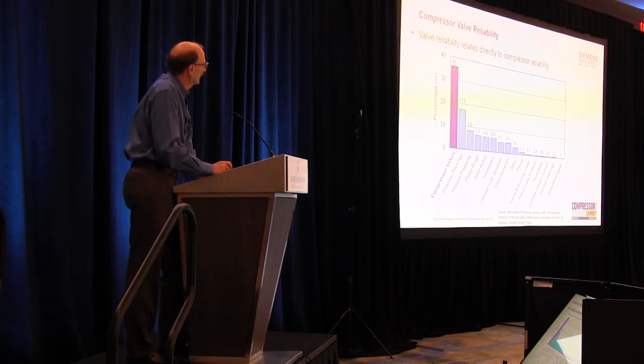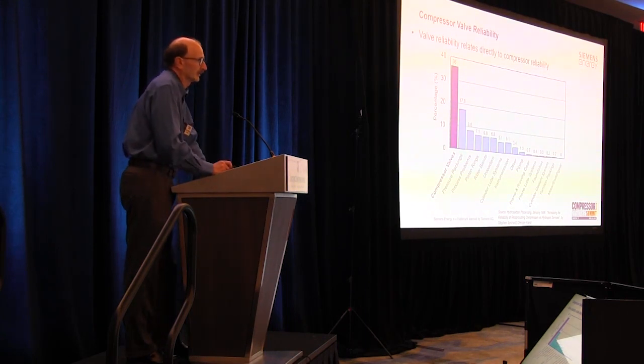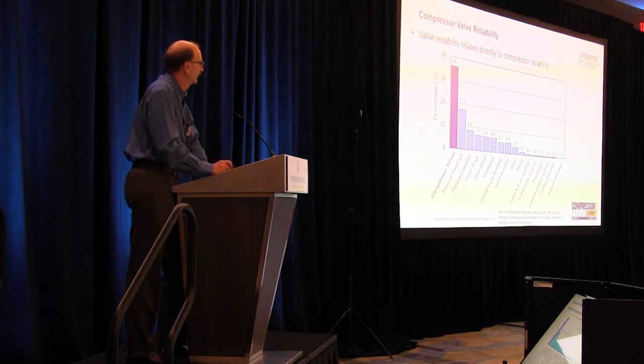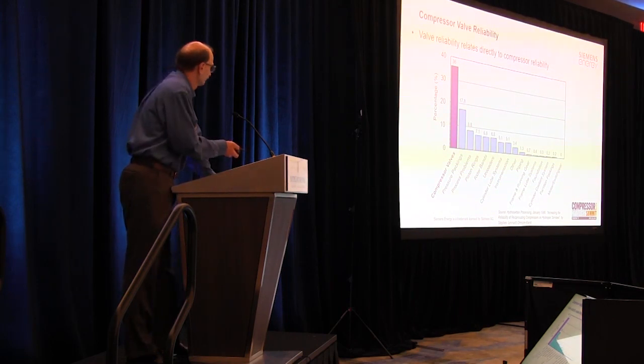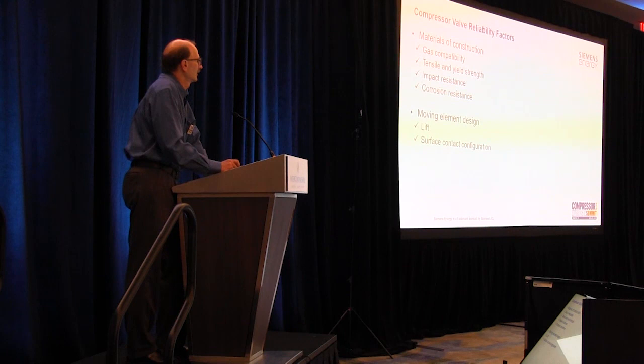A study was done back in 1995 on refinery compressors. Our company, when we were Dresser-Rand, went out and performed a study, asking our customers, what's the biggest reason for unscheduled compressor downtime on your recips? By far, it was the compressor valves. So that's an obvious area to attack to improve reliability. Now, that was back in 1995. Some people say that data hasn't changed much, but it depends. Valve technology has improved quite a bit since then, so that chart isn't true for some people today, fortunately.